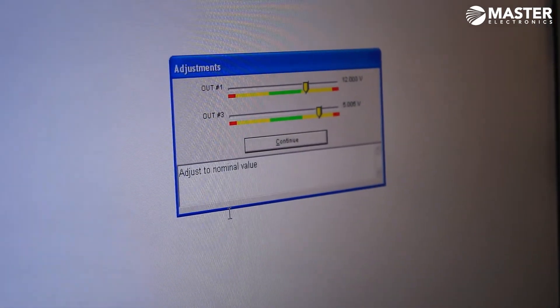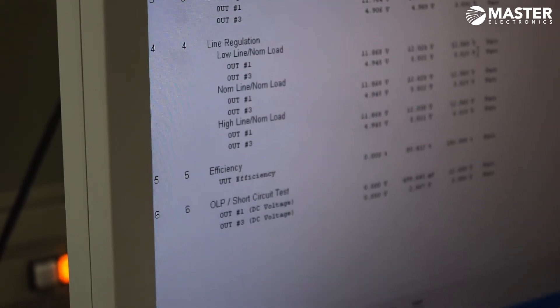We check for proper output regulation when the load or the input voltage changes. In addition, the system calculates the efficiency of each unit and performs a short circuit test on each module.